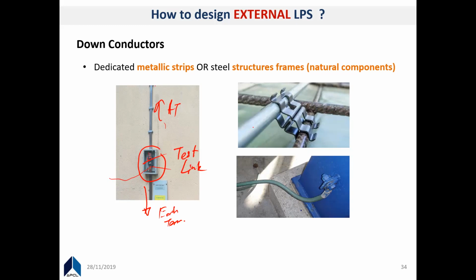So this is a metallic strip, a metal strip. For instance, this is like 25 millimeter by 3 millimeter. You better write this down, because when you do a design, you might have to come up with a bill of materials, a list of materials. So this is typically 25 by 3, or you can go for higher sizes. This will depend on your down conductor requirement according to class and number of down conductors. I will show you the number of down conductors in the next slide.